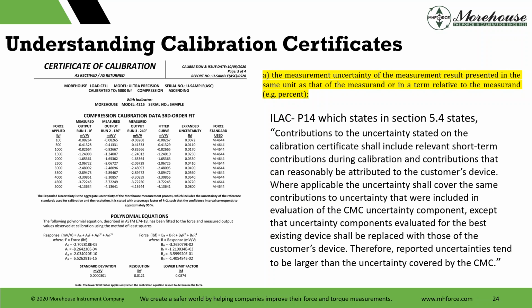For short term, it is generally accepted that the repeatability and resolution of the unit under test be included. That is not reproducibility. ASTM lower limit factor best represents reproducibility. So we take the same things included when we did our CMC. We're doing a dead weight calibration. So in dead weights, we don't have a secondary standard with a lower limit factor. We have dead weight calibration by NIST. So we're going to take our CMC, which included repeatability studies of similar cells, and we're going to add the resolution to it. And we're going to report it.